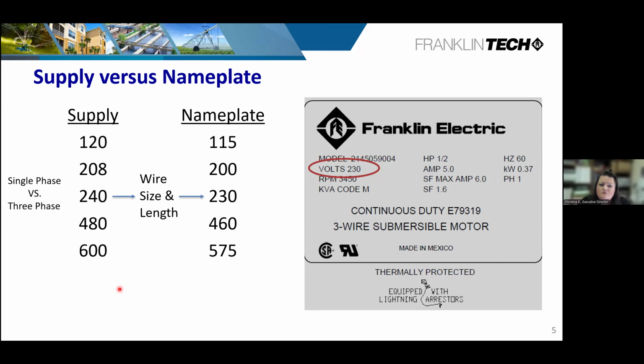So down the line, somebody else's protection is going to be tripping that's pulling off those lines. So ultimately, we have a big issue with the power supply coming in. One is it's 1950, 1960 equipment that's out there. Now, granted, they've updated a few of them or brought some of them up to today's standards, but ultimately what we're dealing with is high voltage. I hardly ever see low voltage any longer.